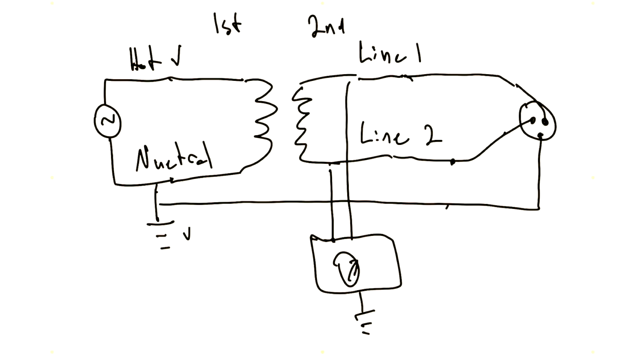Now let's say something occurs within a device and all of a sudden there is a broken wire or something and the ground connection is touching line 2. Somehow these two get bridged. Okay, once again, we have a single fault condition. The line isolation monitor is going to alarm, so there is going to be a warning of danger. However, there is no danger yet. There is not a shock yet.